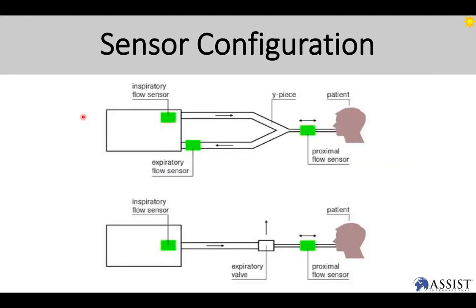Now here is the flow sensor configuration. You'll have a proximal flow sensor between the Y-piece and the patient. You will have an expiratory flow sensor, which a lot of you have seen outside the ventilator. And then you'll have an inspiratory flow sensor as well, usually located on the inside. In its single limb configuration, you will see, again, an inspiratory flow sensor on the inside, and you'll have a proximal flow sensor between the expiratory valve and the patient. But the most widely found circuit configuration is this one on top that we've just talked through. I've seen circuits where people do not use the proximal flow sensor. And so a lot of you are probably familiar with the expiratory flow sensor that you've seen.